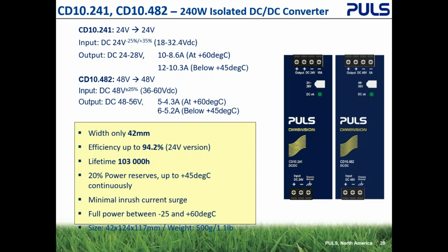It's also used for long runs. You have a light or another remote system a couple hundred feet away, running 24 volts, and you can't run AC out to it for whatever reason. By the time it travels a couple hundred feet, your 24 volt signal, even if you crank it up to 28 or 29 volts, gets out there at only 18 volts. Hook it up to this, and you've got 24 volts again. So it boosts the signal and also eliminates any noise coming in on the DC line.